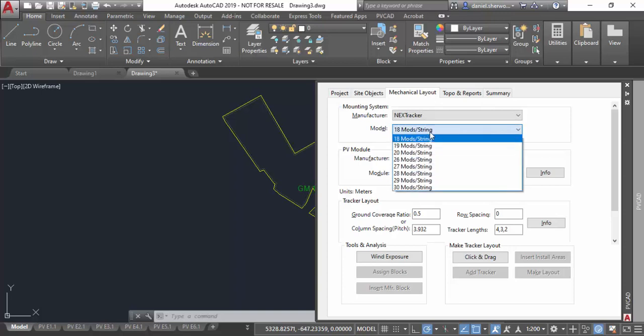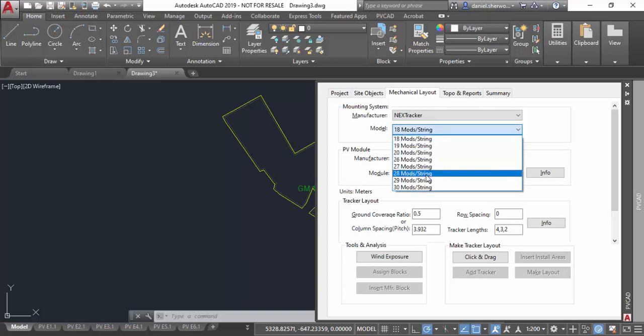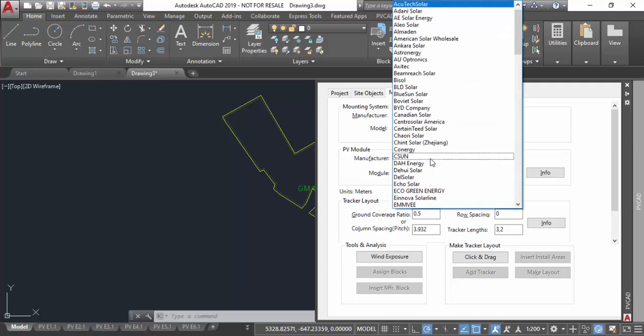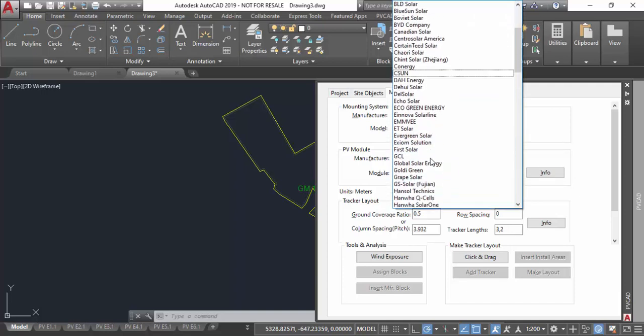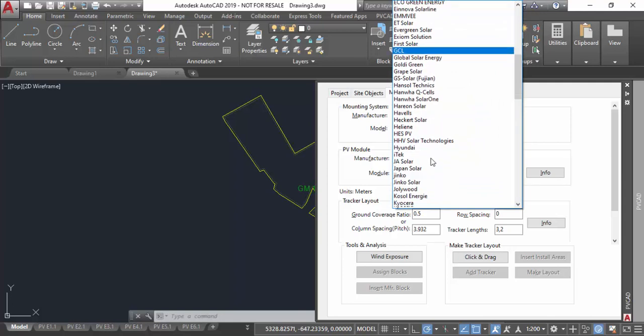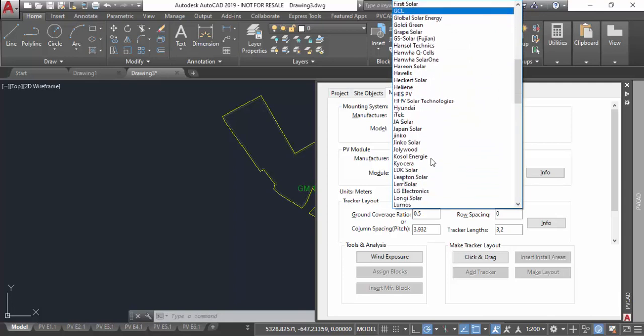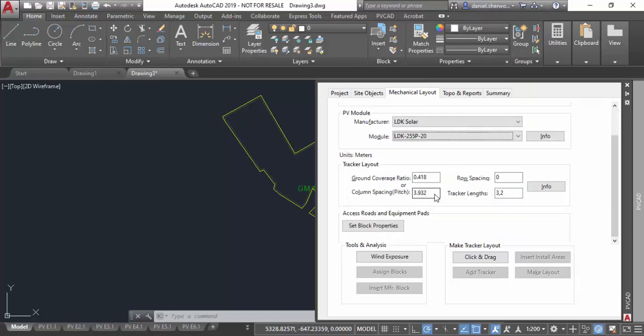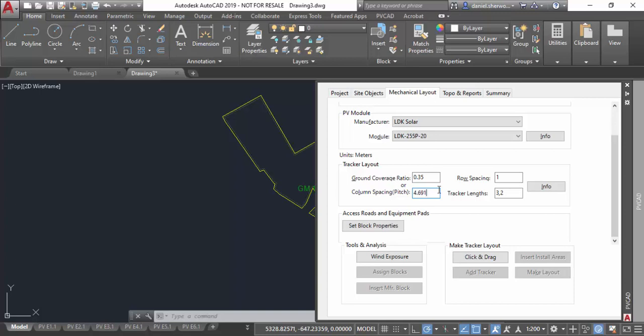After picking the manufacturer, the next thing I'm going to do is select the number of modules per string in that particular tracker and the module from my module database. Using that and the wind speed and snow load that I entered in my first tab, it'll actually look up the specific NextTracker tracker to use on this layout. Next I'm going to enter either the ground coverage ratio or the pitch, as well as the row spacing between trackers in the north-south direction. And then finally this last field tells me if I want to use three-string trackers only, or both three and two-string trackers—fulls and partials for this particular layout.